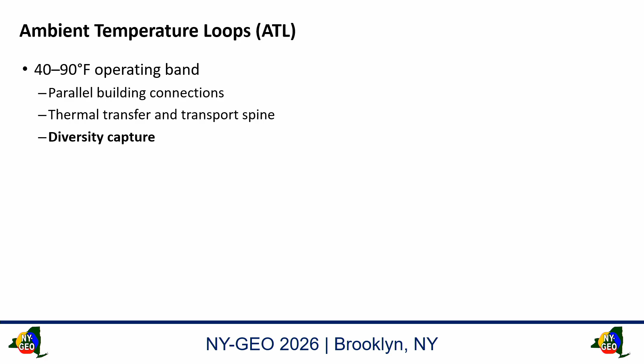I'm not necessarily a tree hugger, but I will hug a tree, especially if it has apples on it. All right? But anyway, we're after that diversity capture. So now if we're going to go to this next step, these are the processes that are required to get to where I want to go. And I'll explain some of these terms. They're new. The advanced thermal response test is precision measurement with a digital twin that captures the volumetric heat capacity. The ground heat exchanger now becomes seasonal storage, not the primary source or sink for peaks.